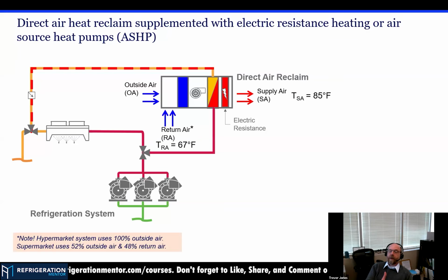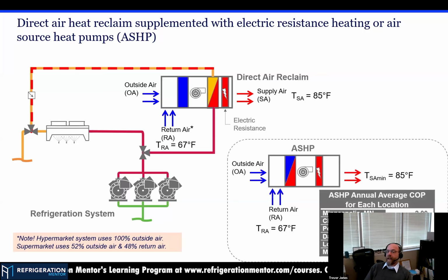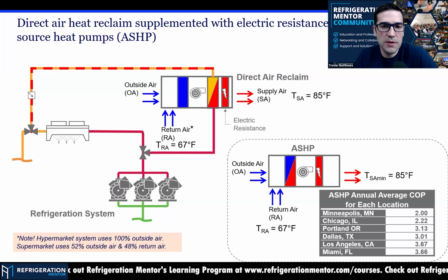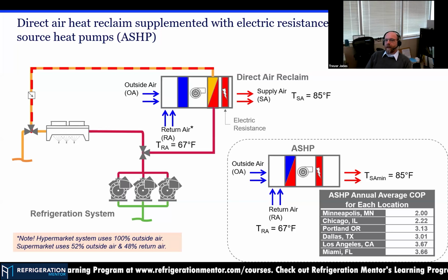And then expanding to the direct air reclaim, again we're now bypassing around the condenser gas cooler with a straight heating coil in the unit. We initially looked at it with electric resistance heat, and then we also looked at it with an air source heat pump component. Okay, and so what was the difference between those two options? The air source heat pumps are far more efficient at introducing heat to the building. And I'm being careful with how I describe them, they're not creating heat, they're introducing heat to the building from the outdoors. So you're cooling the outdoors to heat your building.